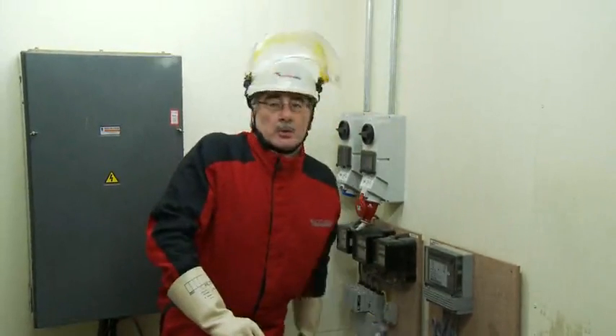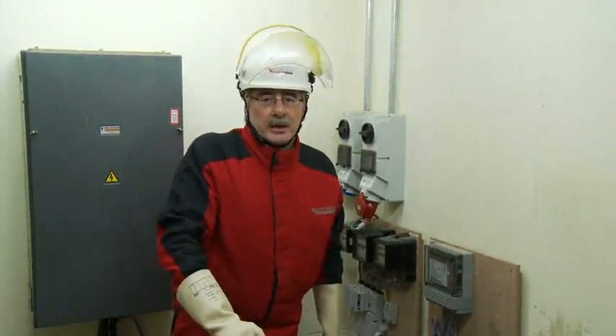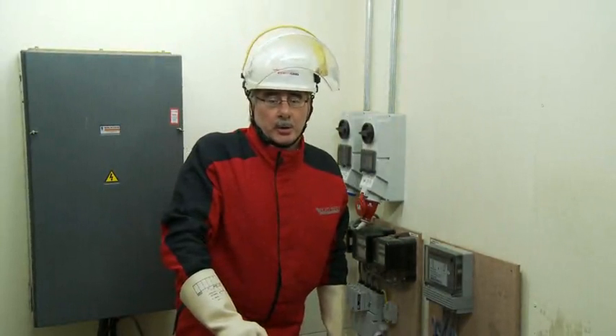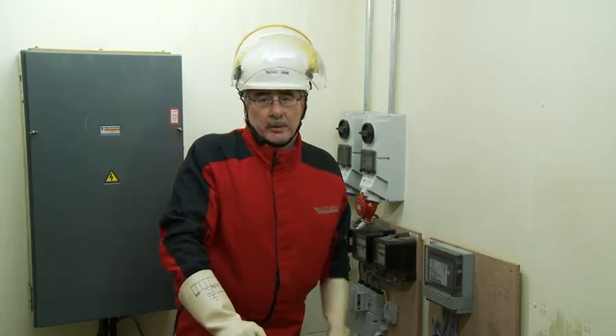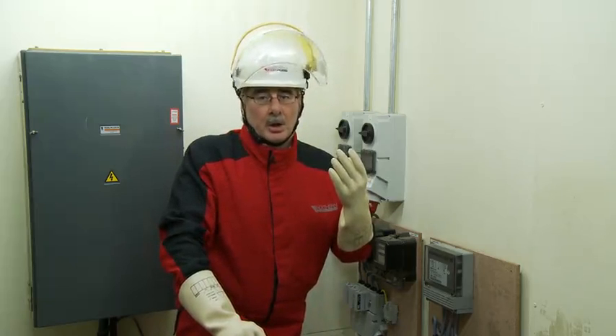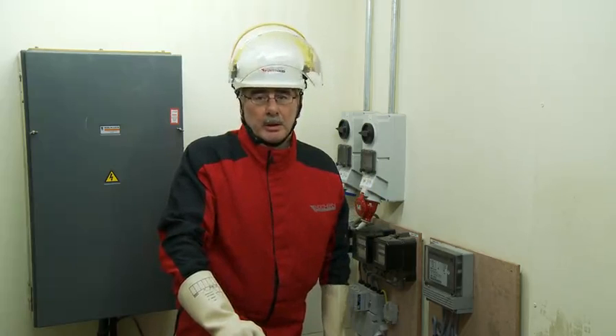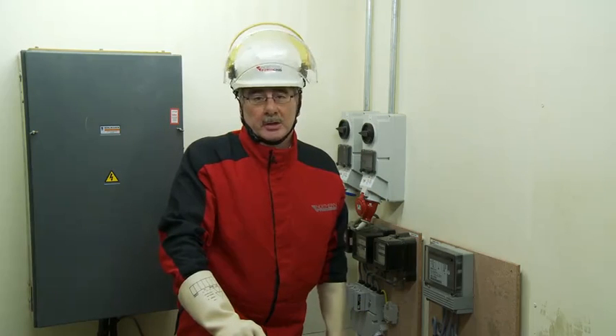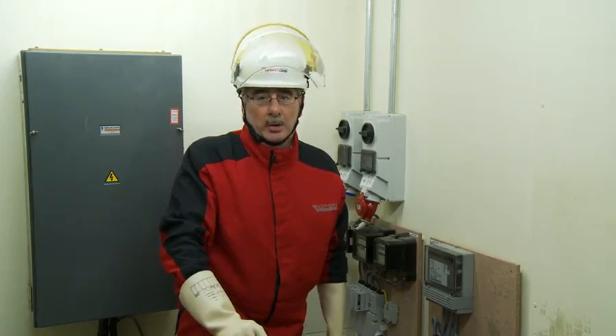Any activity on cutouts such as these 100 amp units here is a single layer option. I'm currently using the coverall together with a full face visor with chin guard, and in this particular case HV gloves, although LV gloves are perfectly suitable. However, if this had been an industrial service unit, a 200 amp unit or above, then a double layer option is required.